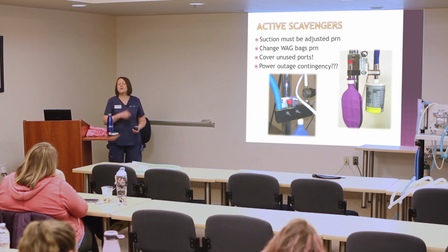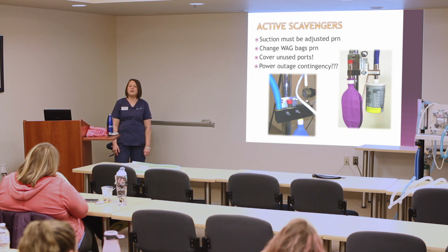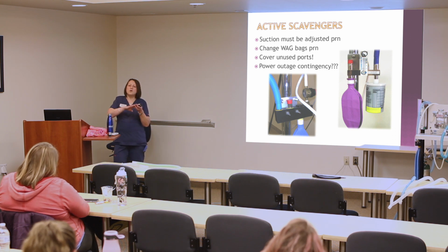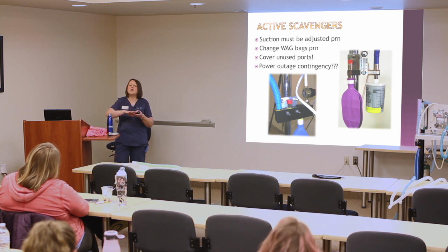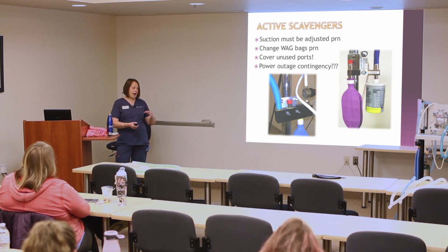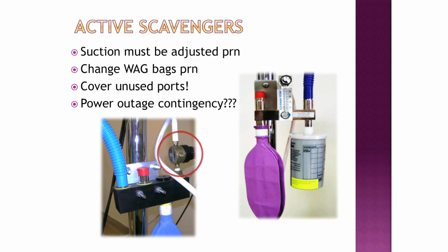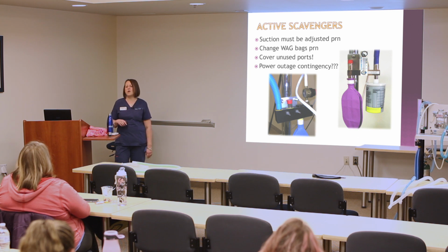And it is conceivable too. One of the things I learned when I was writing this paper on waste anesthetic gases is it is conceivable, whether we're using one machine in the hospital or all 10, that there can be a different burden on the scavenger and on these bags and how full they get. Technically, you are supposed to adjust this knob based on the hospital demand. For the most part, I think right now, even if we were using all of them, it's unlikely that this bag would get big, but if it was, technically, it is your responsibility to say, this is not doing its job, maybe we need to increase the suction here. But I think it's highly unlikely we use all 10 machines at the same time. But this makes sense to me.